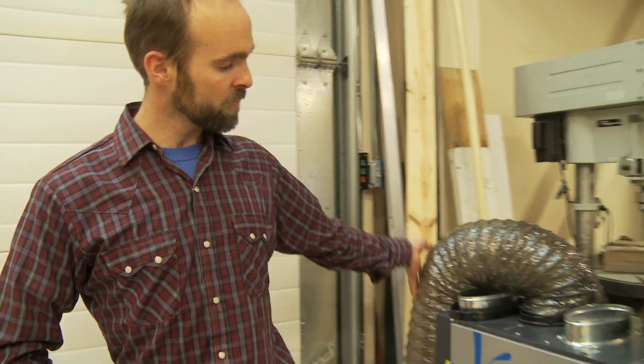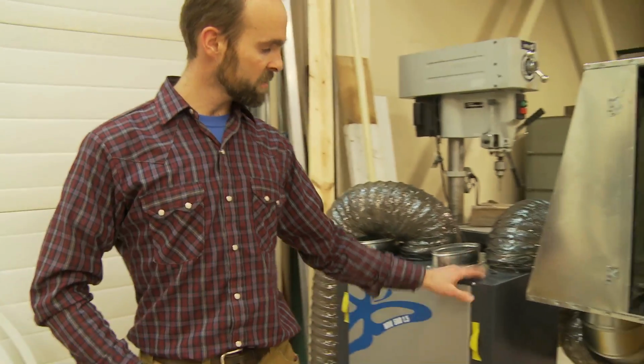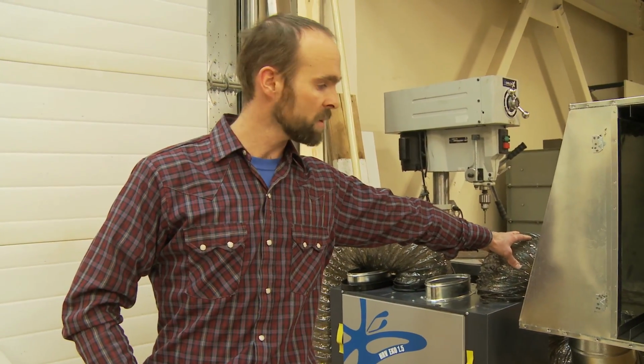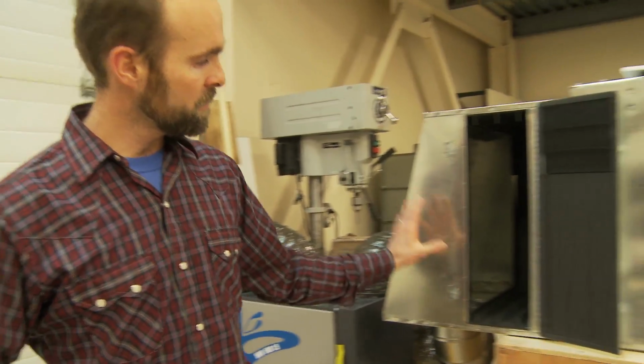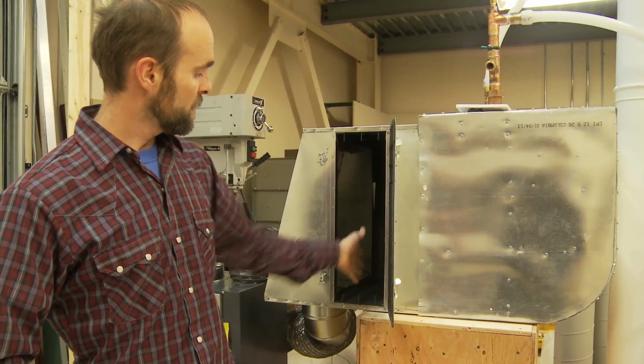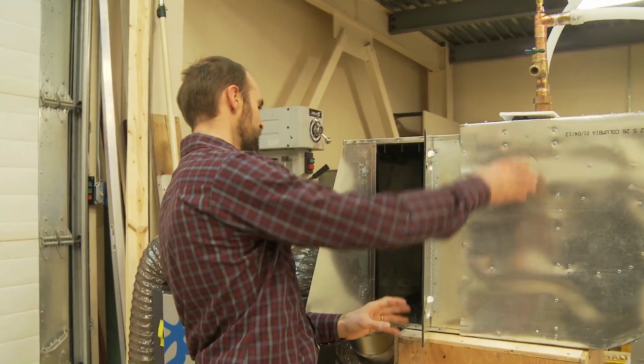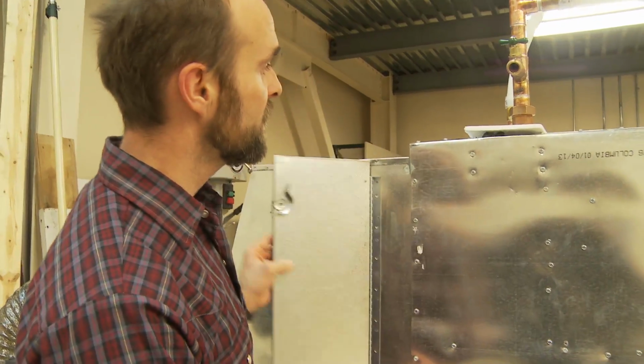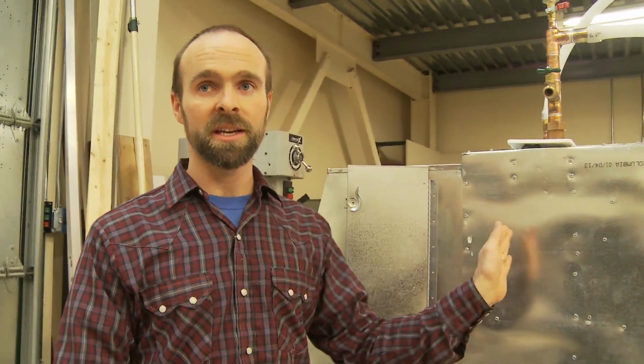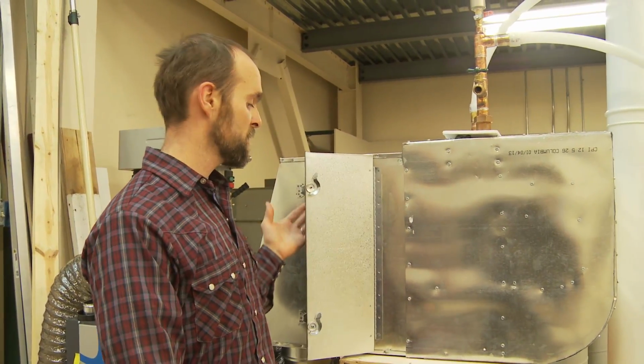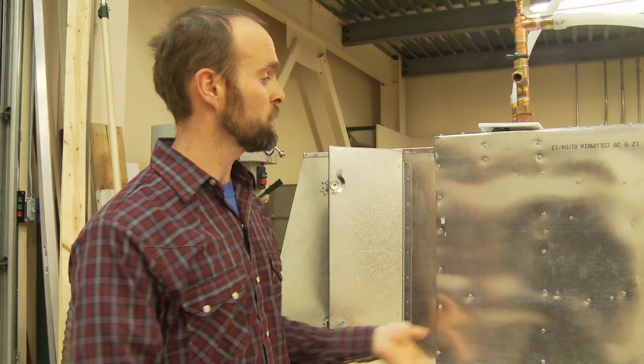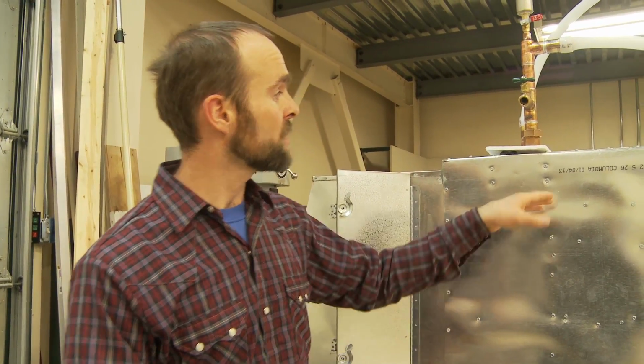We bring our cold, fresh air from outside and recover some of the heat that would normally be going out. This is just supply air that would go to all the rooms in the house, but we're doing something a little different here. We're bringing it into this filter box, a place where we can filter out the air. Right inside here there's a heat exchanger, kind of like a radiator in your car. The idea is that if we pump hot water through this heat exchanger, it's going to warm the air moving across it from, say, 40 degrees Fahrenheit to maybe 90 or 100 degrees. Now we've got this warm air delivered to your room.